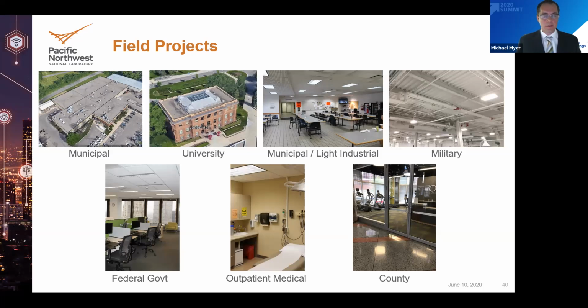I would tell you that was probably one of the harder things to do with this technology, is that on paper, it sounds like it makes sense, but because it's HVAC, it's a little harder to verify in practice that's actually happening. You need to let it run for a week or two just so you can see that data, mainly because the thermal environment outside directly affects your loads inside.